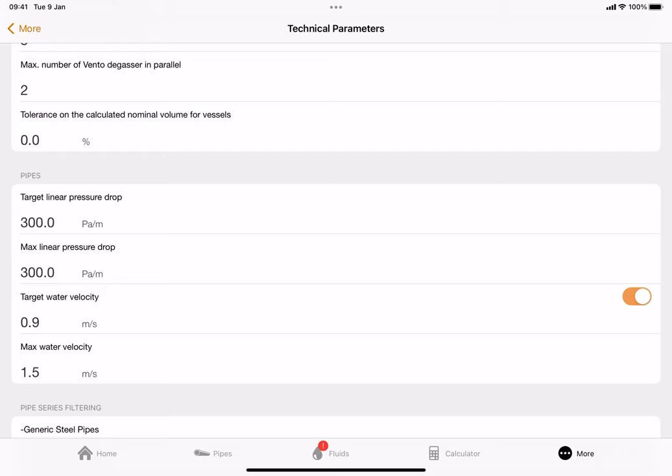CIBSE also states that water velocities should be 0.5 to 1.5 meters per second. I generally design every system - every plumbing system I ever design - to about one meter per second. That doesn't matter whether it's heating flow or returns, hot or cold systems, even mains hot-cold systems - try and design all your pipe work for one meter per second. The reason is: when you start going over one and a half meters per second in velocity you start to get system noise - water hammer and that kind of thing - and you'll also start to get system erosion or possible component failure because the velocity is too high.